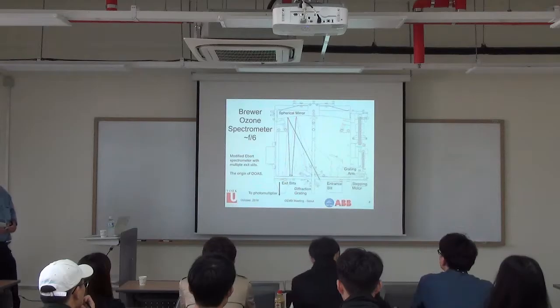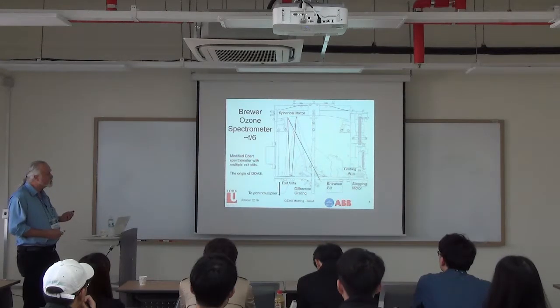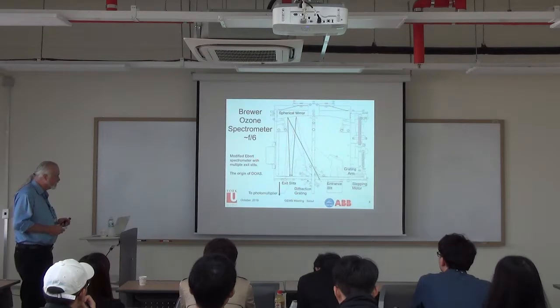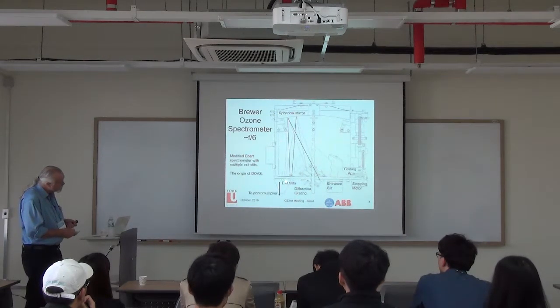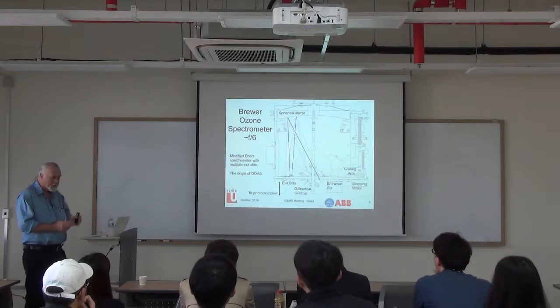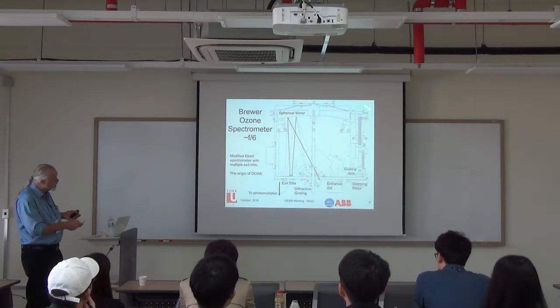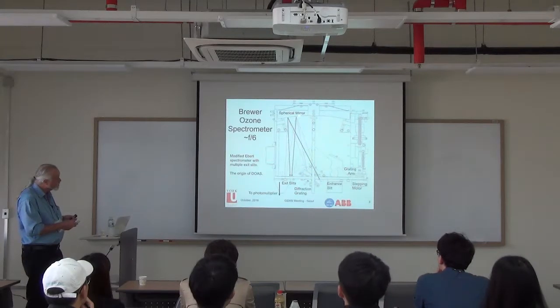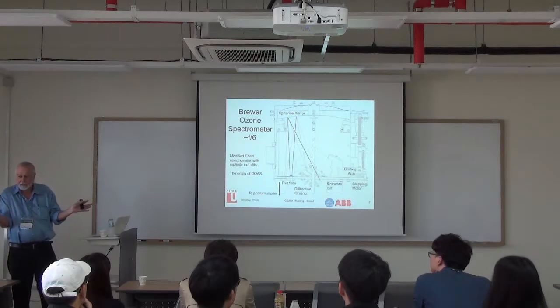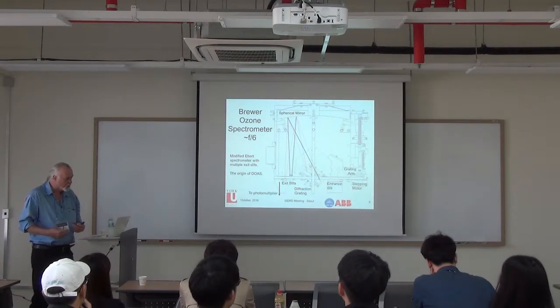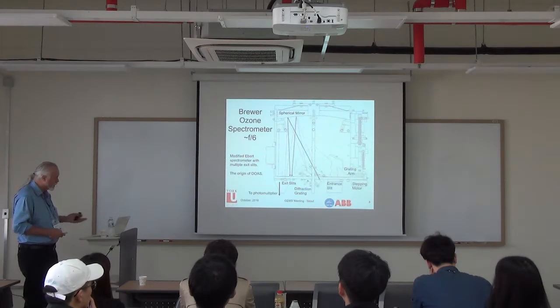The Brewer is roughly an F6 spectrometer. Because it has single individual slits, each slit can only see the mirror due to the solid angle restricted by the slit. This means stray light bouncing around inside the box finds a very difficult path through the exit slit. That's quite different from an array detector seeing two-pi steradians with light coming from all directions. The challenges with an array detector are considerably more severe than with an instrument like the Brewer.